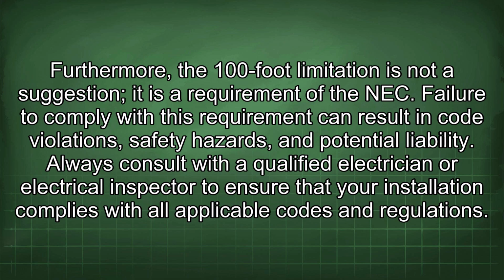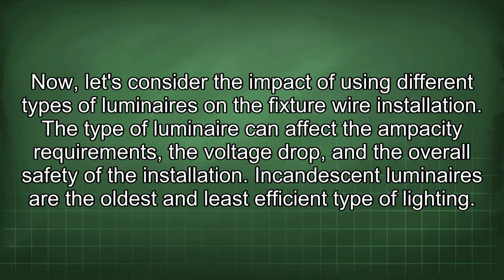Furthermore, the 100-foot limitation is not a suggestion, it is a requirement of the NEC. Failure to comply with this requirement can result in code violations, safety hazards, and potential liability. Always consult with a qualified electrician or electrical inspector to ensure that your installation complies with all applicable codes and regulations. Now, let's consider the impact of using different types of luminaires on the fixture wire installation.